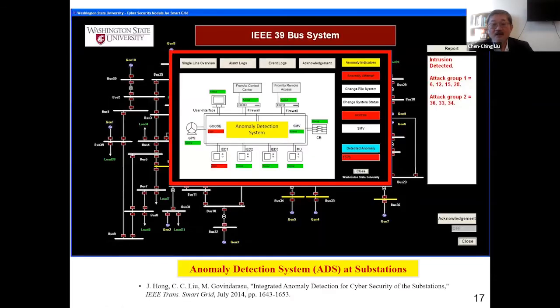That's how we mitigate the system. Another important thing is that by capturing those 1,500-plus packets within the substation, they have not hit the physical system yet, which means the circuit breaker is still closed. Control center operators don't even know something has happened, because you're able to work at the cyber system level and capture those attack commands within the cyber system.